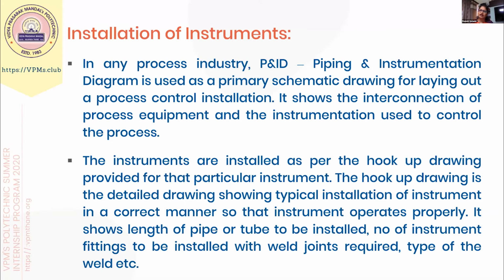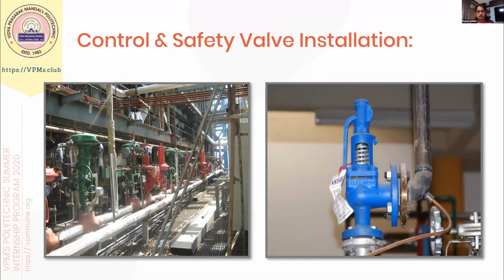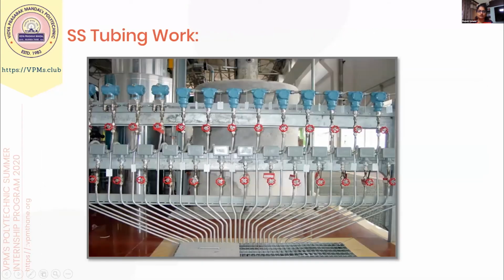The hookup drawing shows the length of the pipe or tube to be installed, the number of instrument fittings to be installed with the instrument, the weld joints, the type of joints, the material of construction, and many more. So this is the control and safety valve installation. You can see this is a safety valve and these are the control valves. This is SS tubing work. Sir has described this. Hookup is a part of it. Yes, of course. For this, fitters are required for instrument tubing.